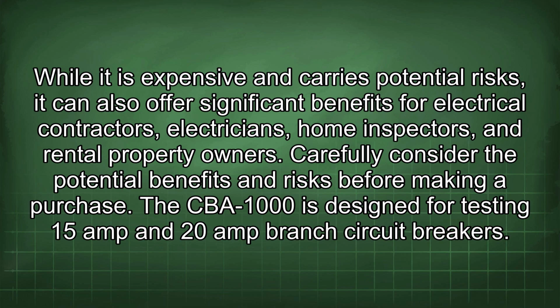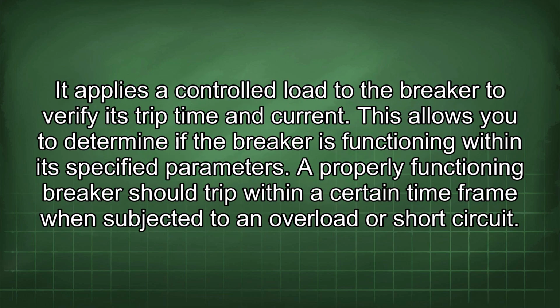The CBA-1000 is designed for testing 15 amp and 20 amp branch circuit breakers. It applies a controlled load to the breaker to verify its trip time and current. This allows you to determine if the breaker is functioning within its specified parameters. A properly functioning breaker should trip within a certain time frame when subjected to an overload or short circuit.